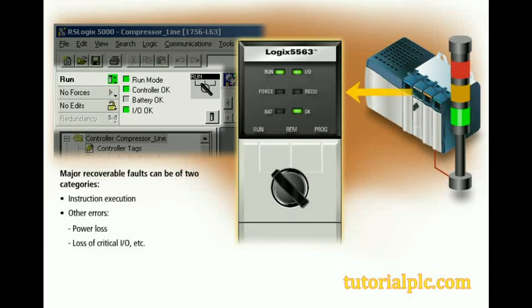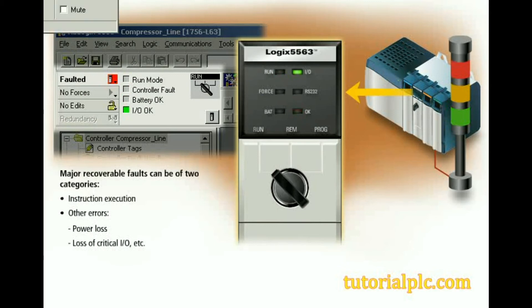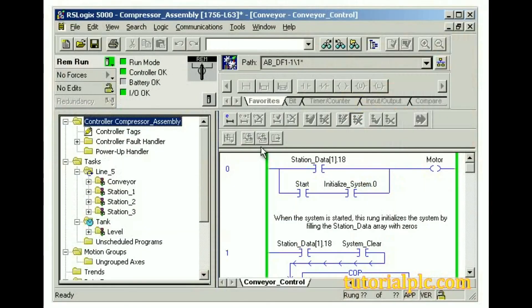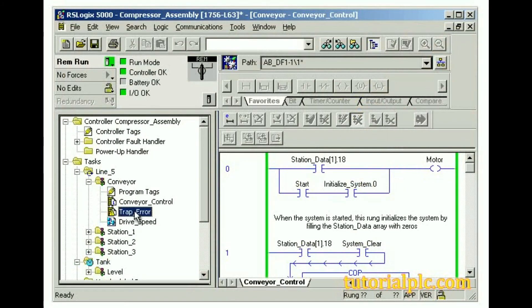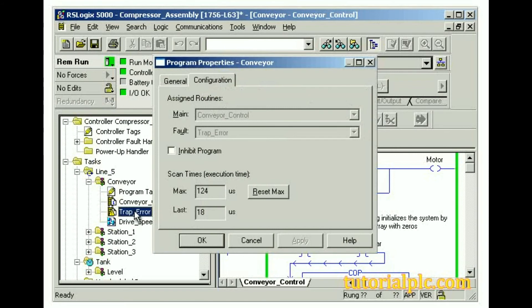When a major recoverable fault caused by instruction execution first occurs, the following changes take place: a major fault bit is set in the controller, and if it exists, an optional user-programmed fault routine is executed. Program-level fault routines normally contain logic to identify a fault. Some fault routines also contain logic to remove the cause of the fault. These routines are created as normal routines and then assigned to be the program fault routine.